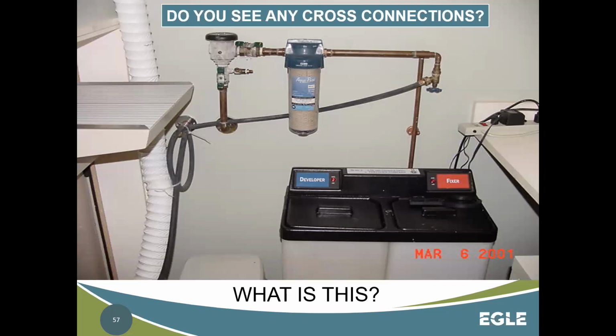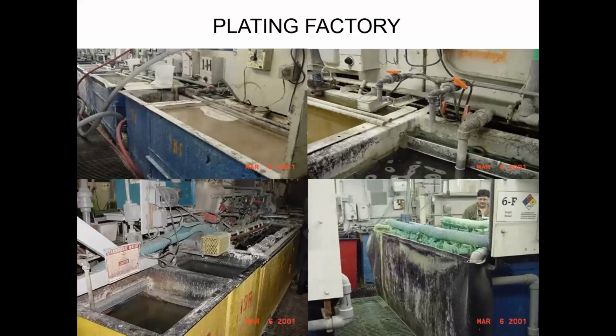So in this case, this is actually for X-ray development. And we've got the tanks down in here that have some pretty harsh chemicals inside of them. They had it protected by this pressure vacuum breaker. The reason this becomes a problem is because they've added this hose bib on the end. And now we've got this hose running somewhere off picture. Which again, this is an example of we had a correct install, we did not have an issue, and now a modification has been made, which might cause a new problem, depending on where this is going.